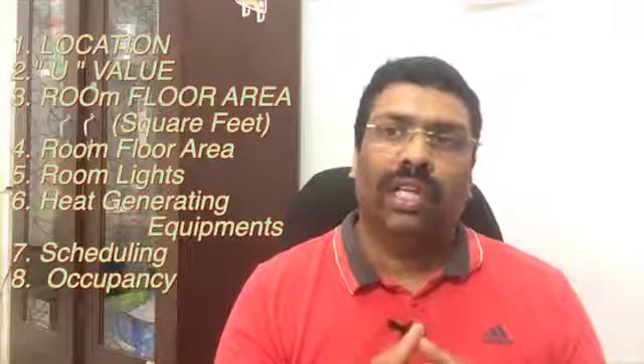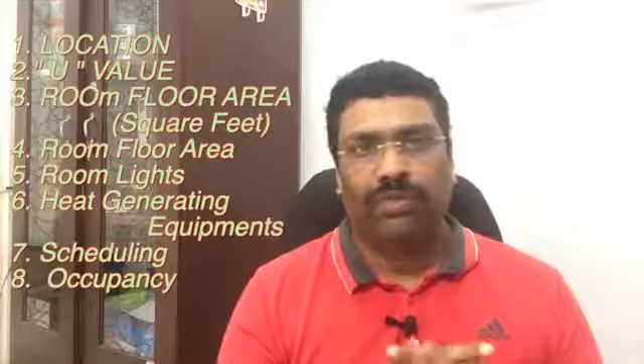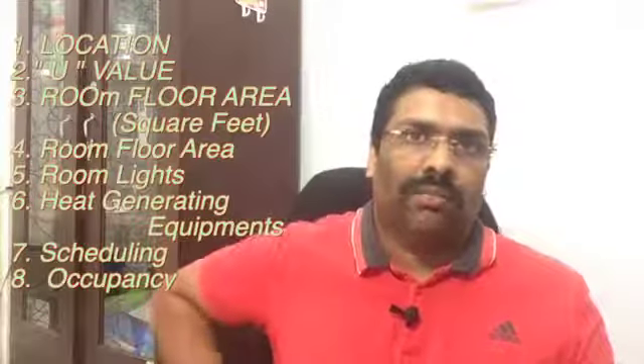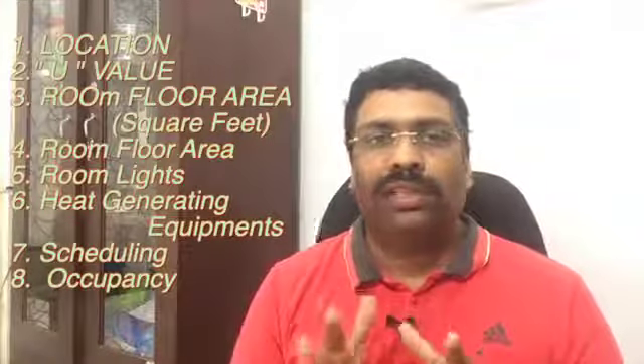The eighth point is occupancy, meaning how many people are in the room. For occupancy, there's a schedule available from the HAP software and from ASHRAE. For example, a bedroom has 2 people and a living room has 4 people. This schedule is available in the ASHRAE handbook that we can consider. From that schedule we can determine occupancy, because occupancy generates two types of heat: latent heat and sensible heat.